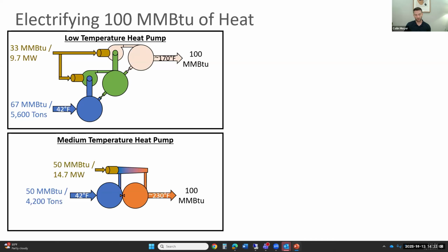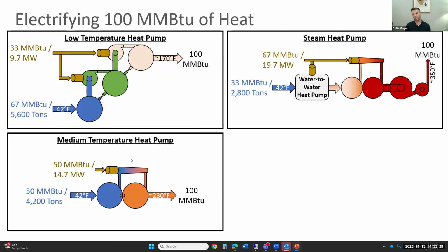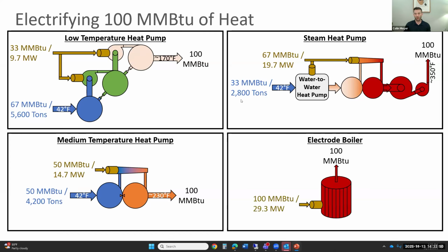If you were to deliver at a higher temperature, though, it's going to take more work to deliver the same amount of heat. So you're putting in more work, you're recovering less from your low temperature reservoir, but you're getting the same amount of heat out. So in this case, you're using 50 units of work. As you go up into steam heat pumps, you get even less efficient. You're looking at, in this case, a COPH of about 1.5. So all to do the same thing here, where we're looking at making 100 million BTUs per hour of heat, if we need to make that at about 350 degrees, we're going to need 67 of those units to come from work, and we only recover 33. And lastly, with an electrode boiler or any kind of electric resistance heater, of course, you're going to need 100% or possibly a little bit more than 100% of that input energy to make 100 million BTU per hour output.